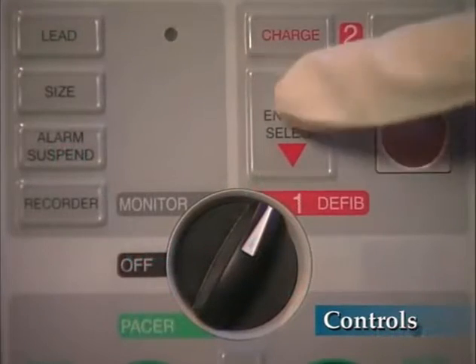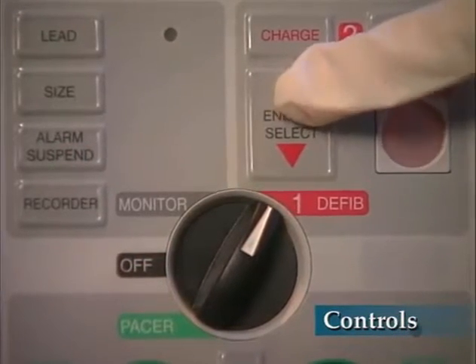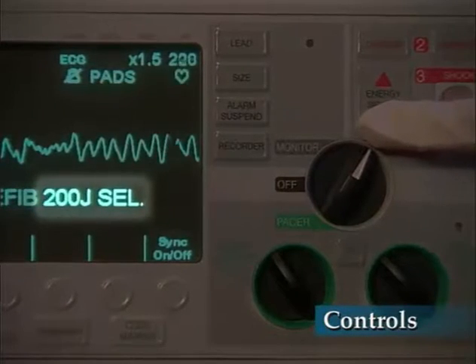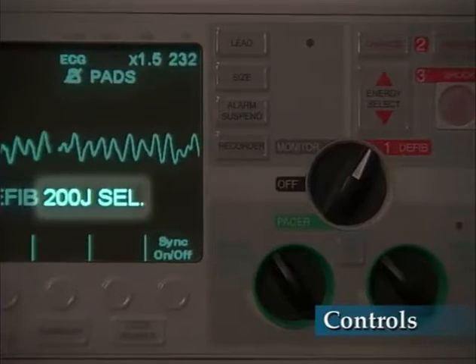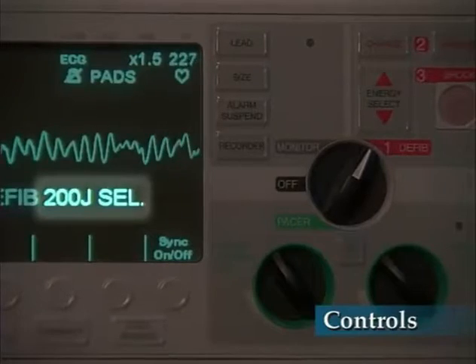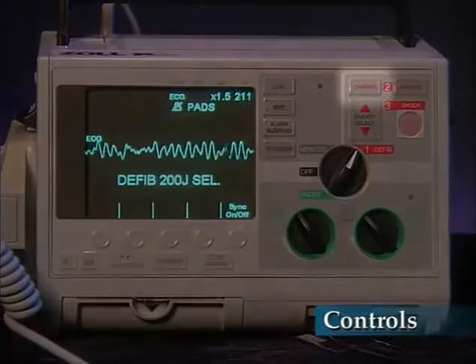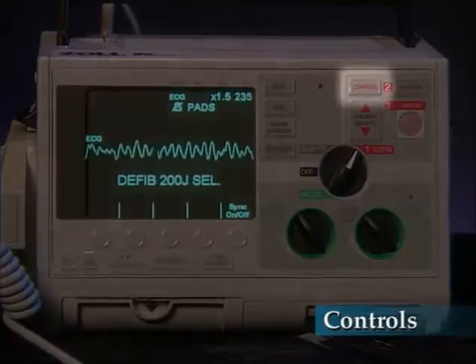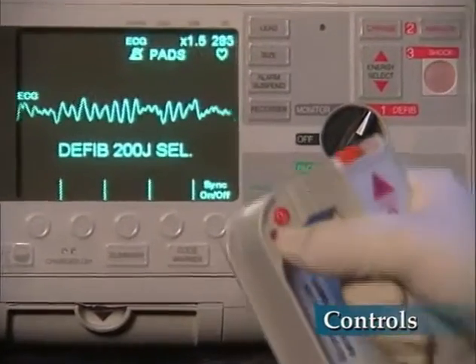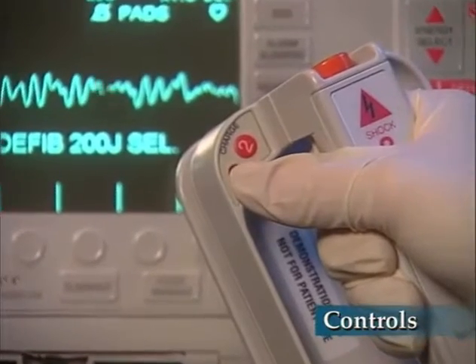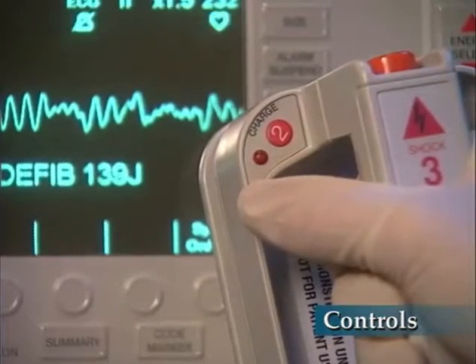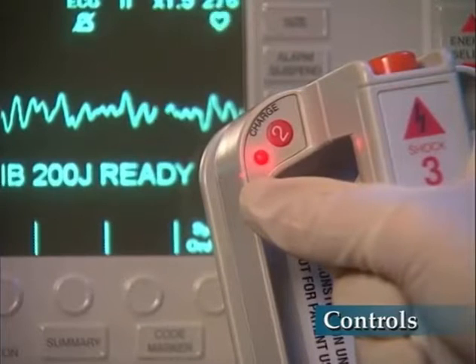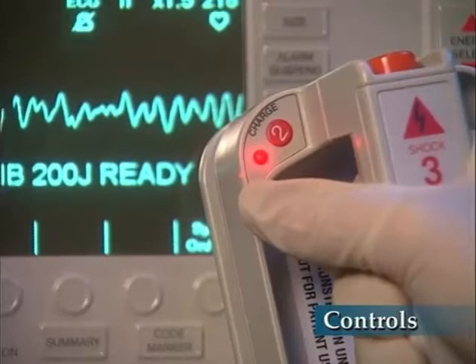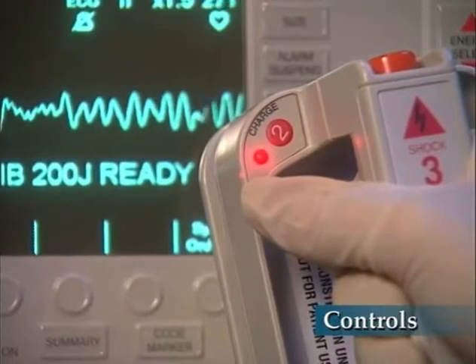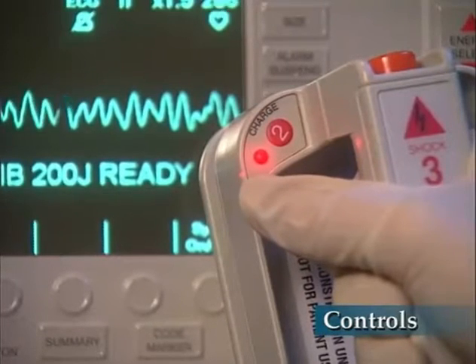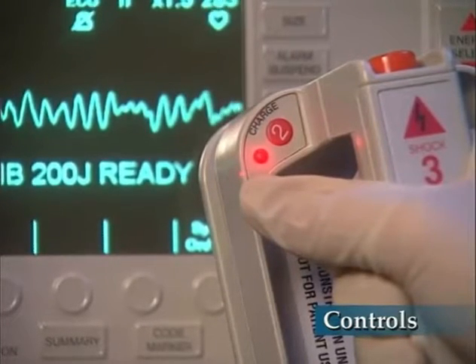There are 2 arrow buttons for changing the defibrillator energy level. Press and hold the up or down arrow buttons until the desired energy level is indicated on the display. To charge the defibrillator, press the charge button on the front panel, or if using paddles, the charge button on the apex paddle handle. Charging is shown on the display. The charge indicator on the paddle lights up when the defibrillator is charged and ready. When the selected energy level is reached, the message "Ready" appears next to the energy display on the monitor.